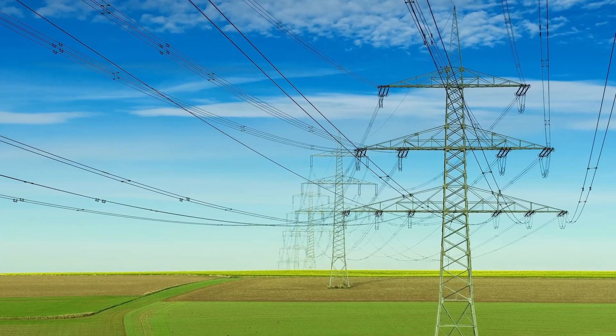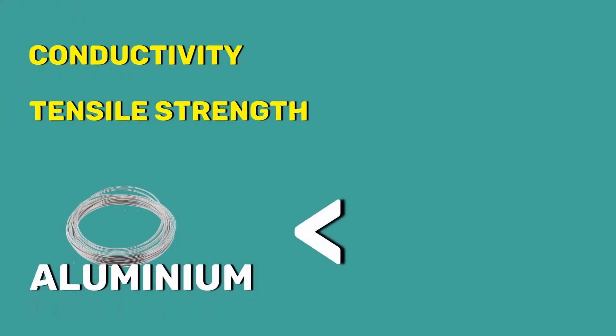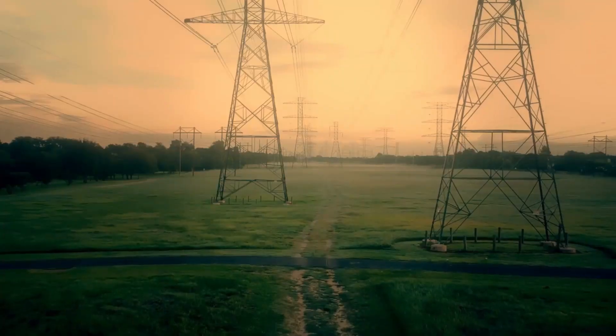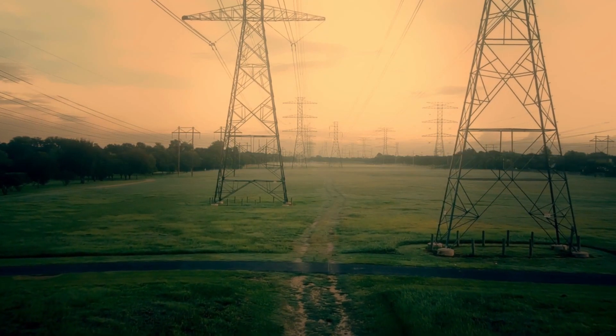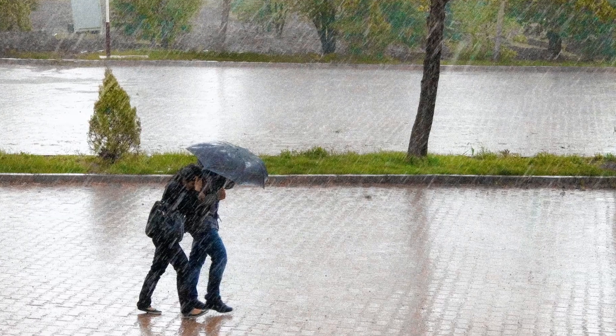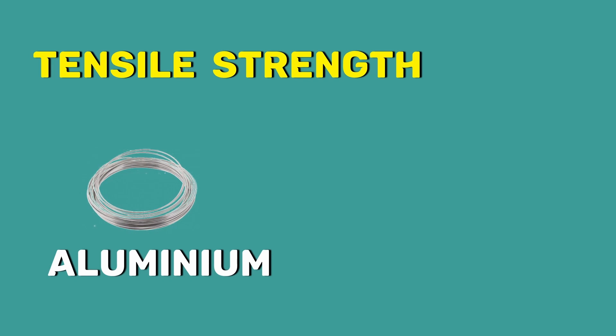However, nowadays we are using aluminium instead of copper. Even though the conductivity and the tensile strength of aluminium are less compared to copper, the cost and the weight of aluminium are low. The transmission line should have the highest tensile strength because it has to withstand heavy rain and wind. So, to increase the tensile strength of aluminium, steel is added to it.